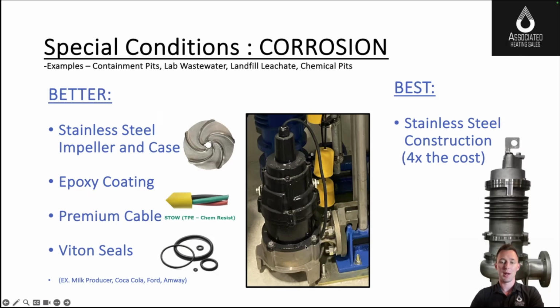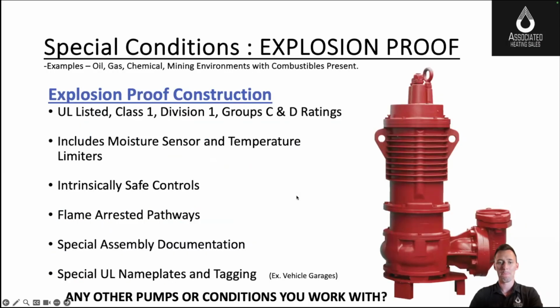So what we'll do in this hybrid option is we'll make the case and impeller, where the fluid touches this pump or goes through this pump, all stainless steel. We'll take a cast iron motor shell and we'll paint it with a chemical resistant epoxy paint and put a premium cable on the pump. And this will last quite a ways. This has been very popular in that different price category.